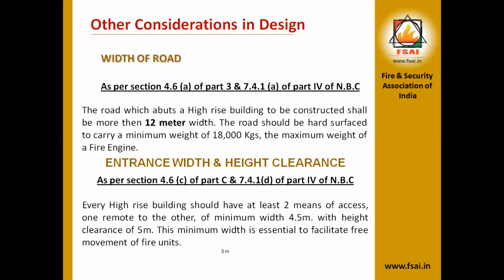The first is the width of the road. As per section 4.6a of part 3 and 7.4.1 of part 4 of the NBC, the road width should be a minimum of 12 meters for high-rise buildings, because the fire tender should move along the building. So the road width should be more. The road should have a hard surface to carry a minimum weight of 18,000 kgs, the maximum weight of a fire engine. In case of any fire emergency, the fire tender comes close to the fire. So the weight of the tender is 18,000 kgs, and the road must be designed to carry the load of the fire tender.